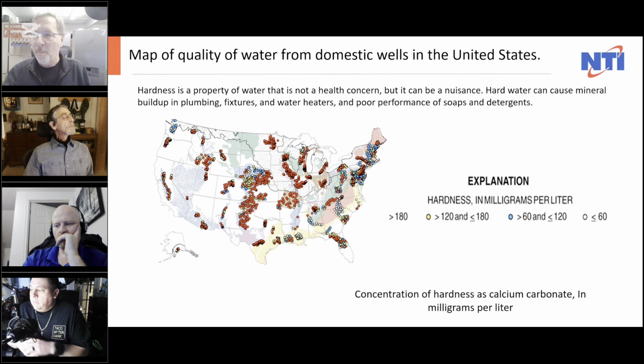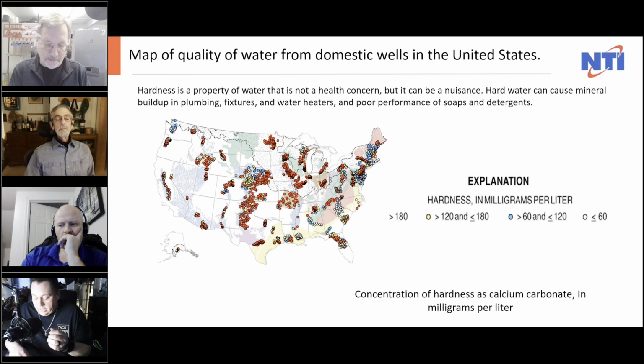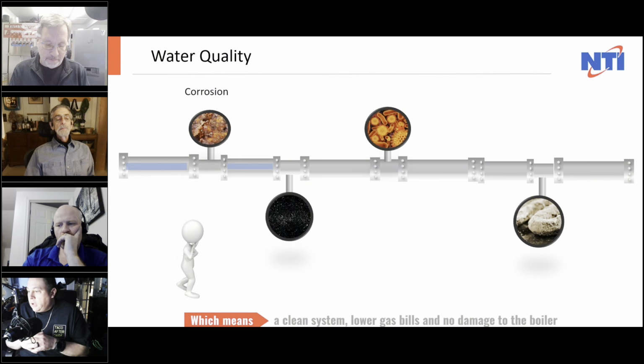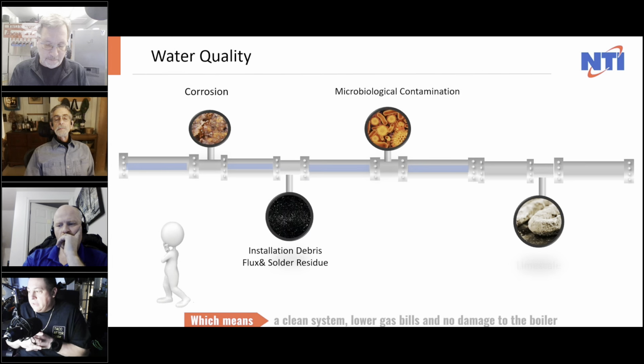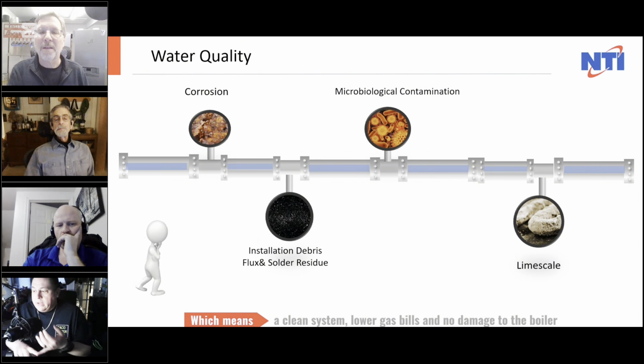We went through and looked at what type of flow we were getting, and pulled the circulator out. It was seized up. We put the new circulator in, the boiler fired right up, and satisfied the tank right away. I've had a couple of situations like that already, so that's something we need to look at. We also need to educate the homeowner that they need to keep up on things like that. What goes through our system? There's a lot of things that are passed through our system, especially if we have radiant systems.